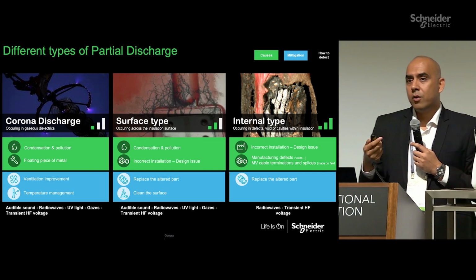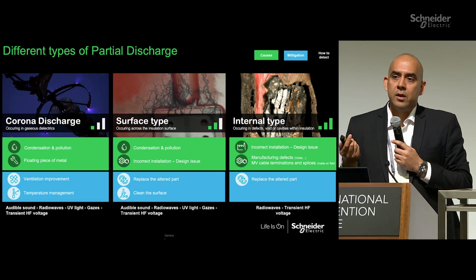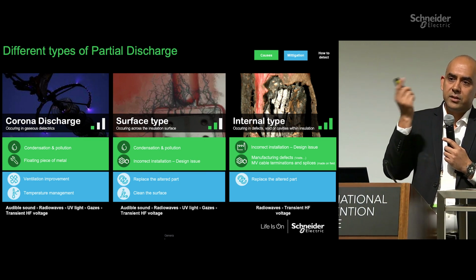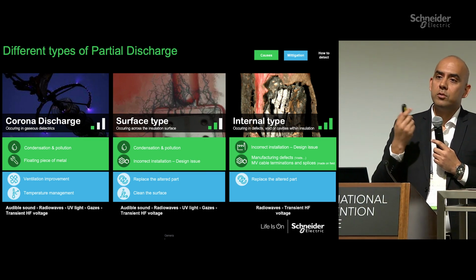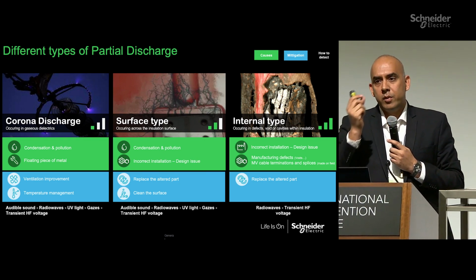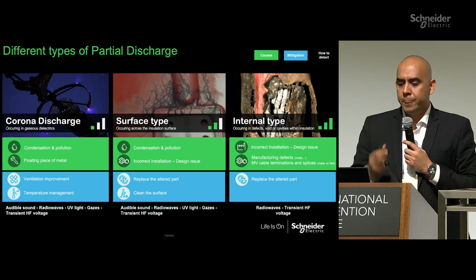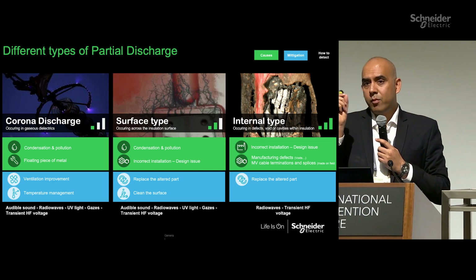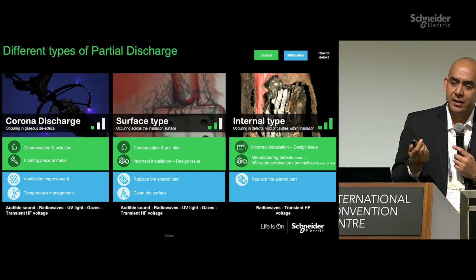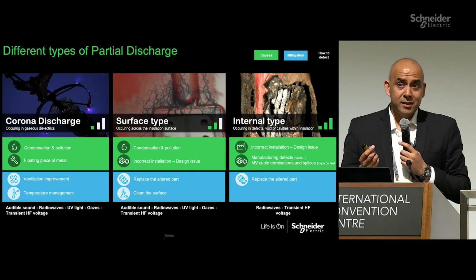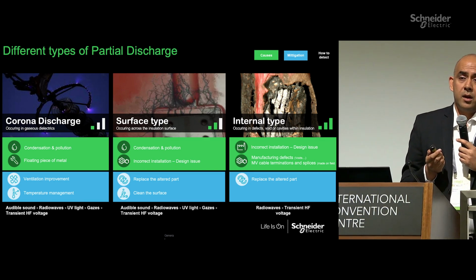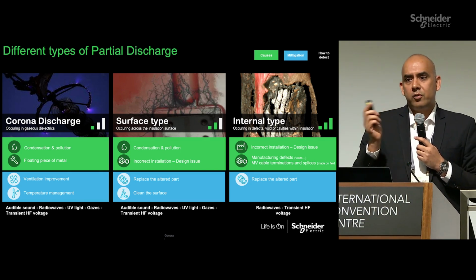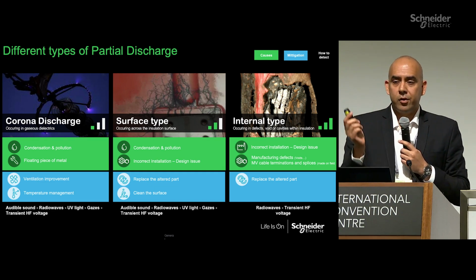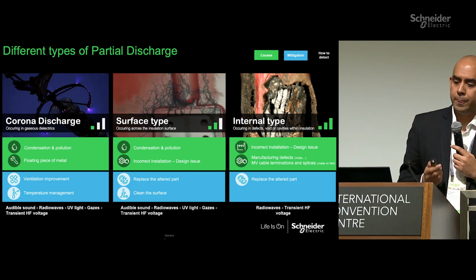Of course, with the sound, you have radio waves, and also if there is an arc which is developing, you have light, and you have ozone gas which gets created because the air is getting ionized. And of course, there are small micro transient voltages which are getting discovered. So corona discharge is something which is quite common. It can be dangerous, but of course, it's a phenomenon which can be controlled in a way because it's visible.